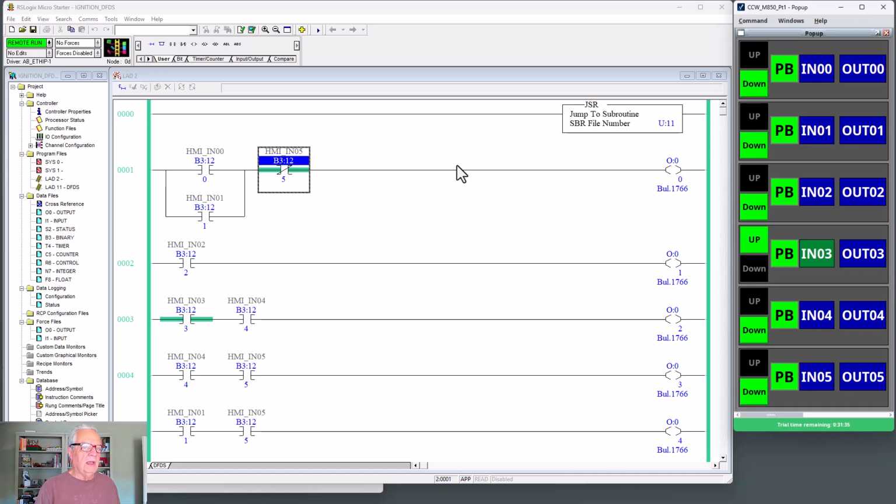If you have a photo eye that's looking for cartons, and a carton is on the move and passes by it, if you use the toggle, which you do on most simulators, and you forget to turn it back off, then you may wonder why your logic's not working correctly, when in reality, instead of using a maintained on, you should have just pushed the button, let go of the button, and the carton has gone by the photo eye. That was the whole intention of having a 4-state input field device simulator.